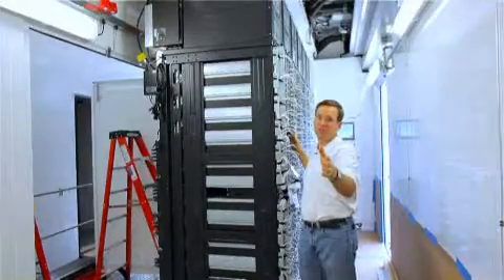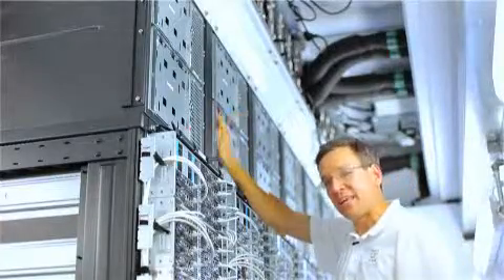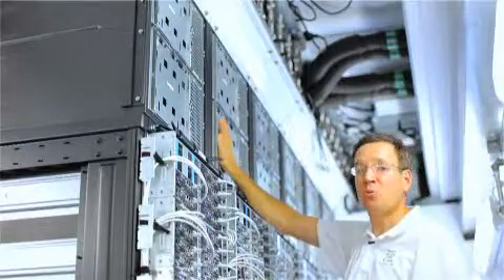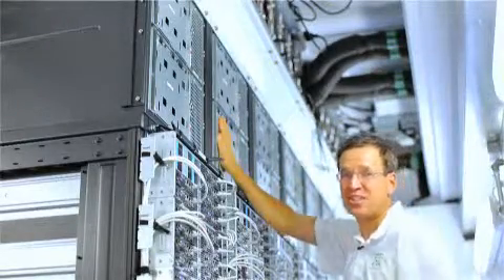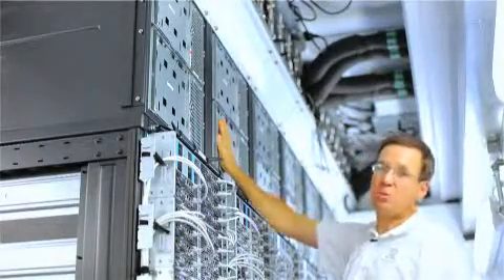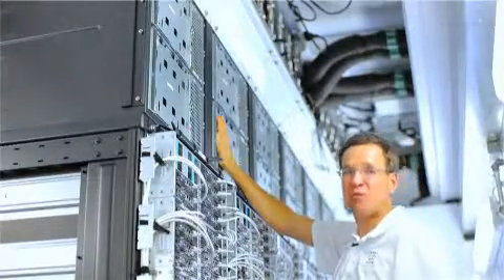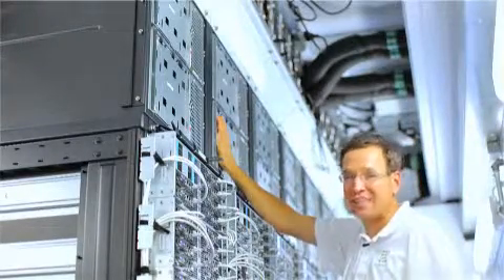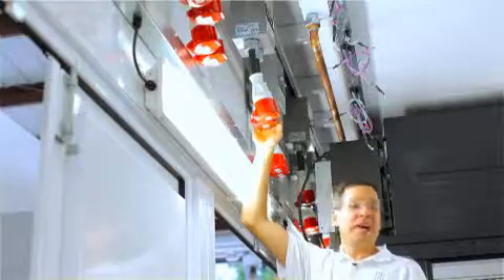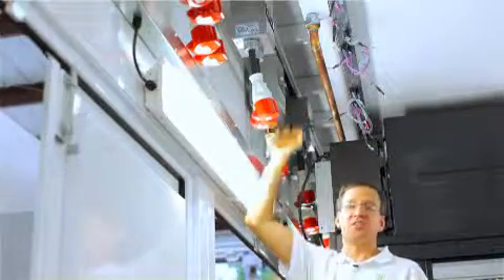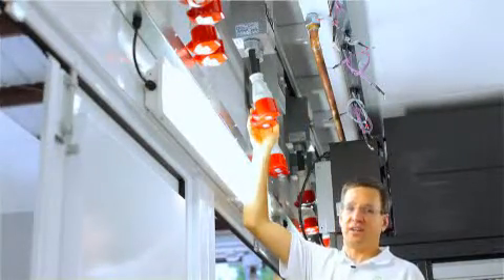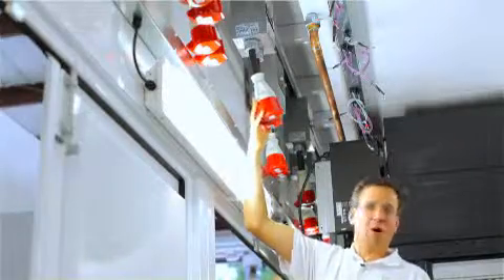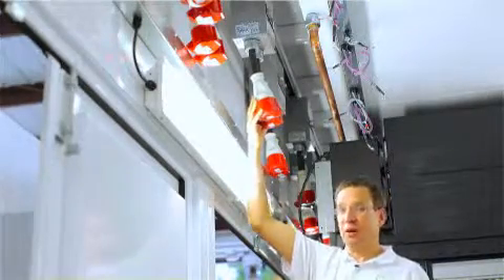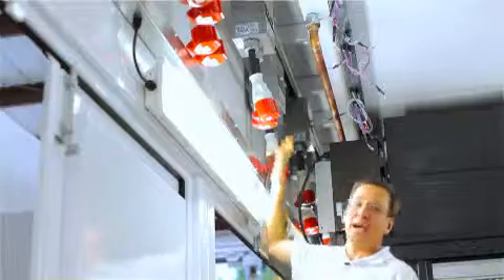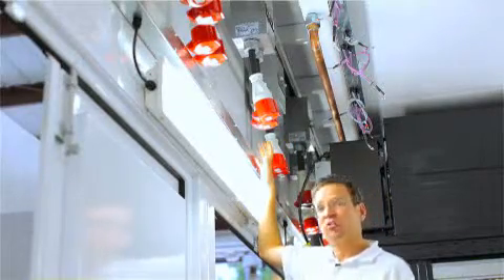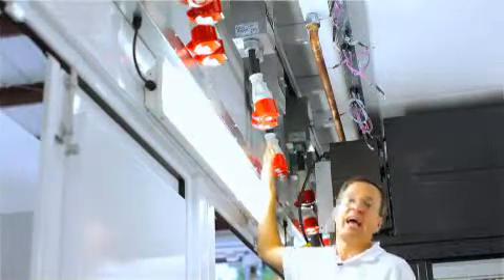The racks have over 20 kilowatts worth of in-rack UPS that's enterprise class and serviceable. It's also a big OpEx and CapEx savings versus long lead time facility level UPS. We have industry standard power buses like you use in your data center. 2 17 kilowatt connectors from every drop and a pair of them, so we actually use 3-phase power, so we deliver the same power at half the current.